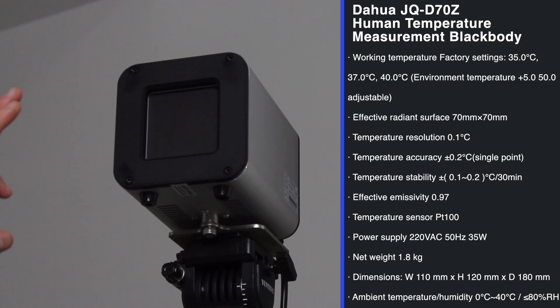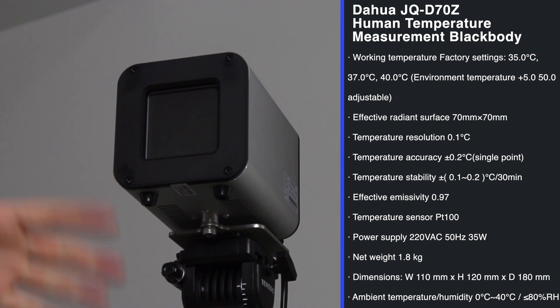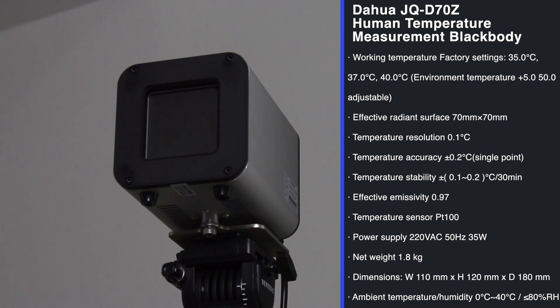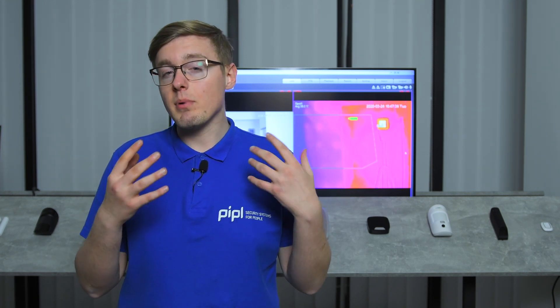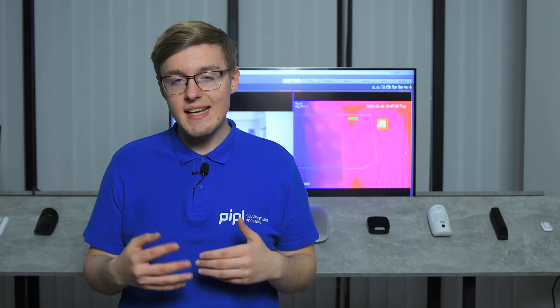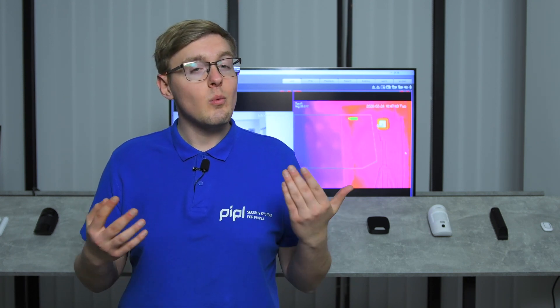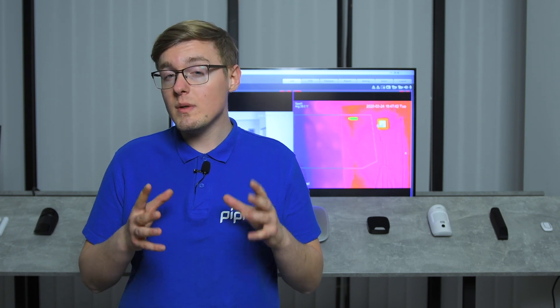The task of a blackbody calibration device essentially is to produce and maintain a specific constant temperature used as a reference point for the thermal camera, and it is adjustable. On a practice, every time when a person passes through the camera's measuring site, the camera correlates a person's temperature with the temperature of a blackbody that produces a constant temperature while the people temperature will always differ. And this is how the high accuracy is achieved.